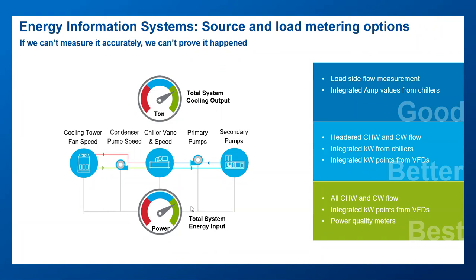So at a minimum, for the 'good' level, you want to at least measure and set up long-term trends, really important for the production of chilled water, hot water, steam, etc., that you're delivering to the facility. And at least hopefully power for your largest users, your primary equipment, your chillers, your boilers, etc. Get the big ones right.